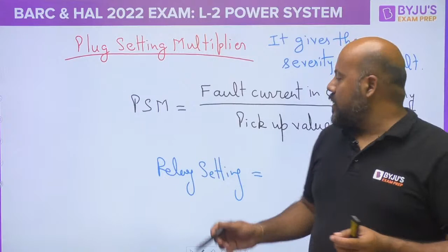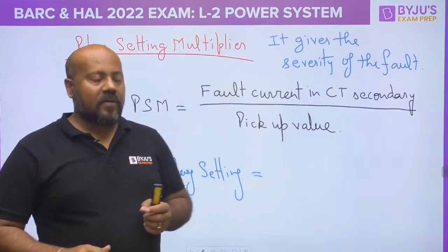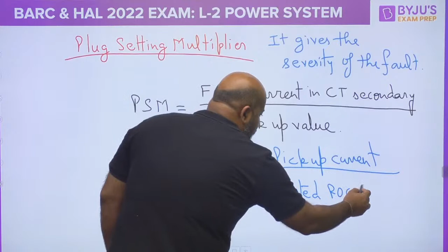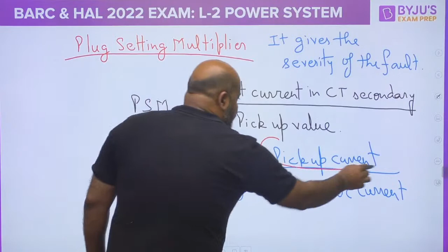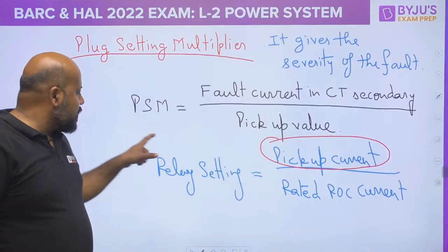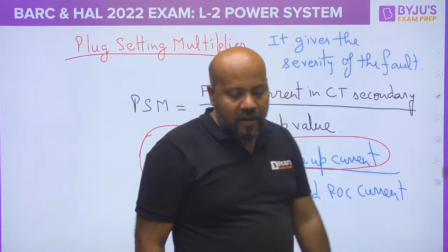Now what is the actual understanding of relay setting? Please try to understand. Suppose you design a relay and you say, sir, this relay is going to operate whenever the current is more than 5 amperes. That is, the pickup value of the current is 5 ampere. I will say, okay, great job done. But in my power system, there may be 100 different cases where the pickup current has to be different. So it is not always that I need only 5 ampere as the pickup current. So do I have any flexibility in deciding the pickup value of the current of the relay? Yes. And that flexibility is a relay setting.